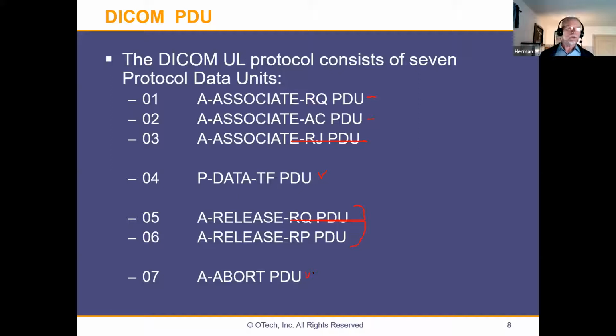So what does the PACS do? It is listening, and at a certain point in time, it will time out. So how does it do that? It sends a reset, an abort, because otherwise these associations will be left hanging open. So an abort is typically done at the time of a timeout, number 1. Number 2, I've seen quite often that an abort is done by standard by any device before it starts to talk to the connection.